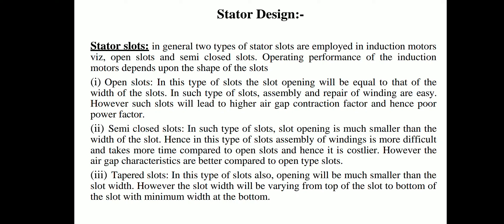The first slide shows stator slots, which are generally of two types employed in induction motors: open slots and semi-closed slots. The operating performance of induction motors depends upon the shape of the slots. In open slots, the slot opening is equal to the width of the slot. In such slots, assembly and repair of windings are easy, however they lead to higher air gap contraction factor and hence poor power factor.